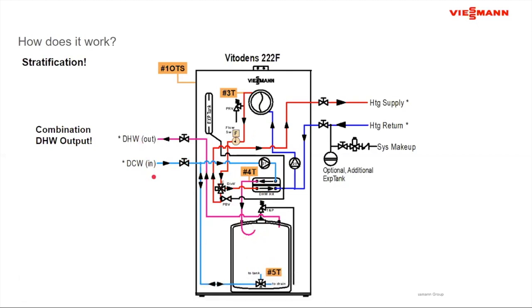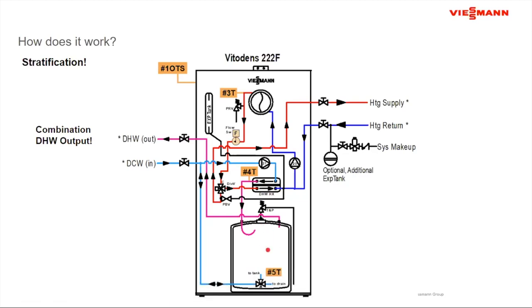So that hot water comes in here. If the demand is greater than what is coming out here, which is about 3.3 gallons per minute, then I will continue to produce hot water but also draw off the storage. Out of all the methods, this is going to give you the best performance over, let's call it, a 10-minute period of generation.